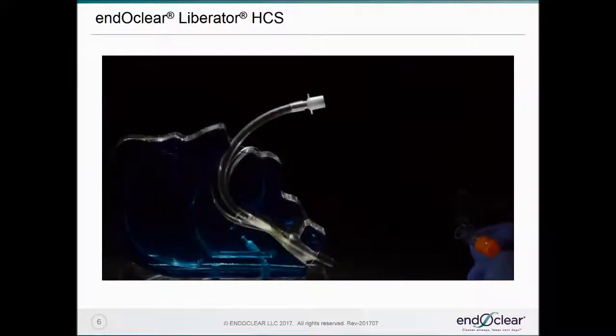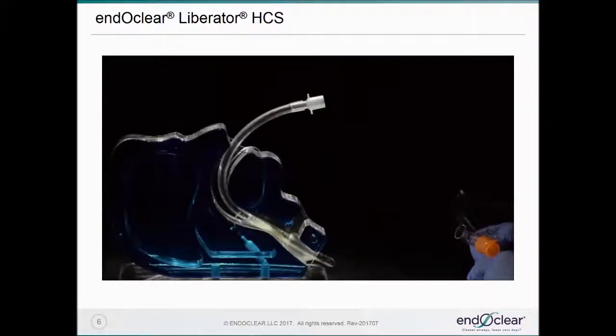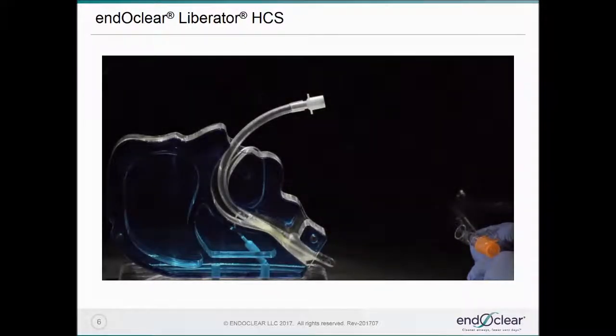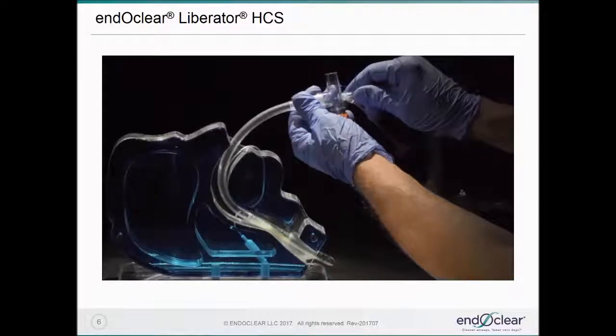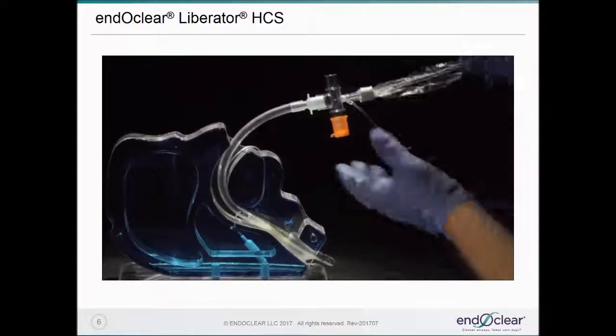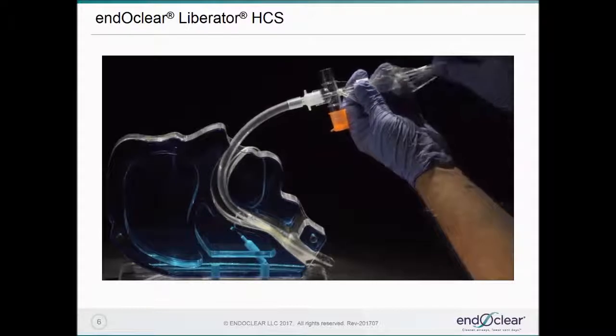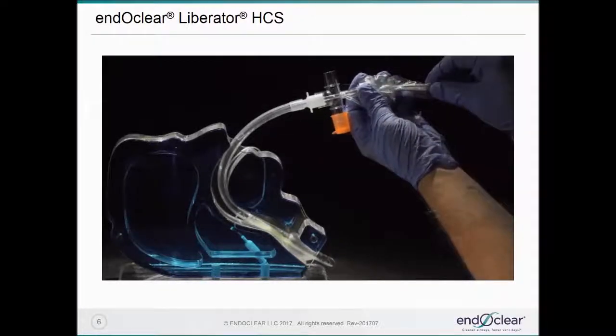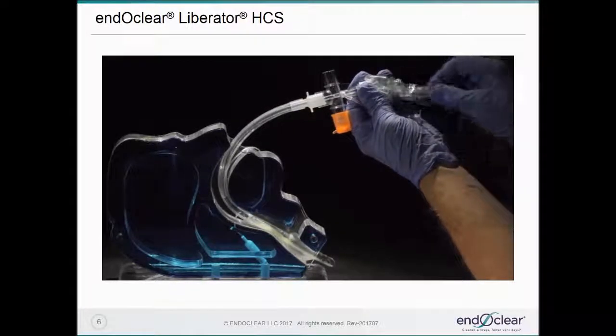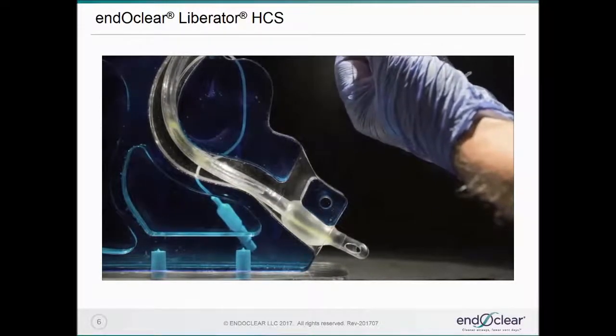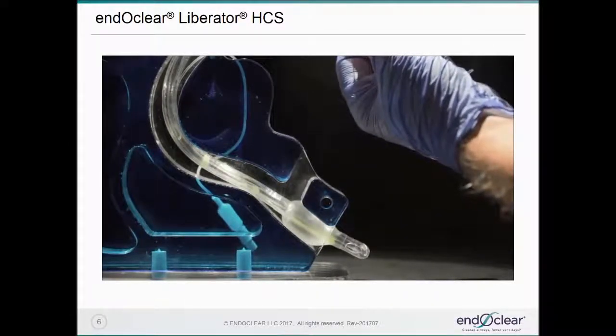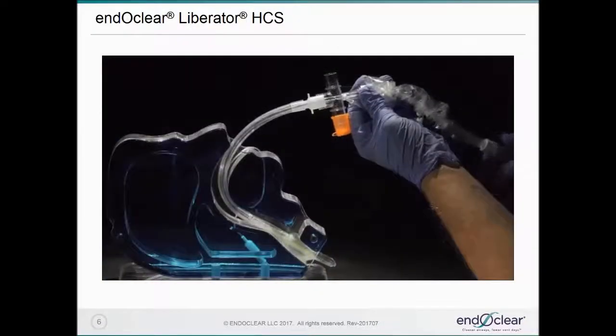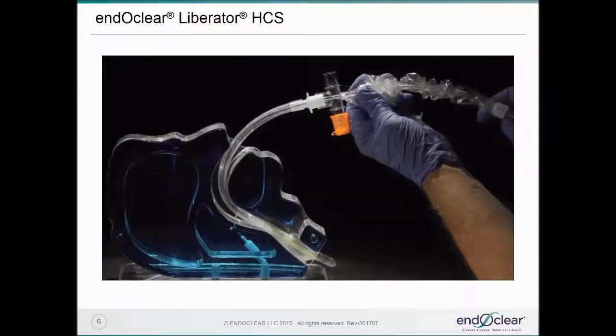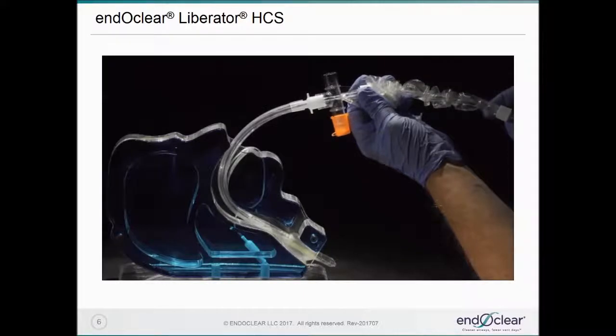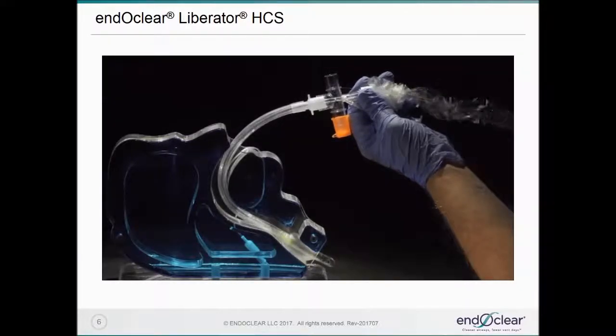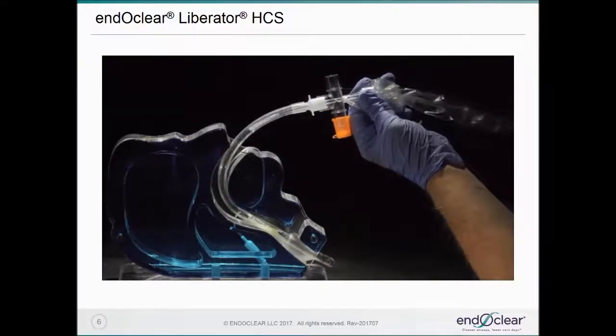This is an 8 millimeter endotracheal tube inside a see-through model of the human head and trachea. I'm going to connect a standard suction system to that. This is actually a 16 French catheter. It's very stiff. Can conceivably do injury if put too far out the end of the tube and into the carina, for example. And now I'm going to apply suction to the end, getting any material off the end, and then pull it back through the tube.